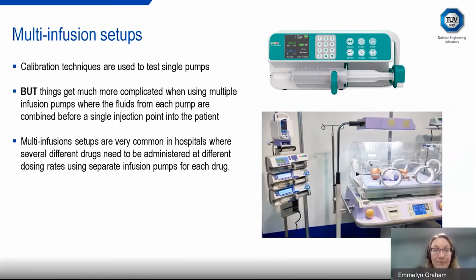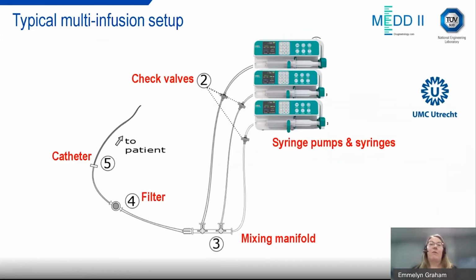So we're going to cover some of the issues and complications with using multi-infusion setups and the impact on the flow rates. So this is just an example of what maybe a typical multi-infusion setup would be like. This is quite a simple setup. So we have 3 syringe pumps and syringes. And then the fluid is flowing from that. We've got here some check valves. This makes sure that there's no backflow of the fluid back into the syringes. We've got a mixing manifold where the fluids are commingled before flowing into a single infusion line. You may have filters. This is to remove any air bubbles or any other issues, and then into a catheter and then into the patient.